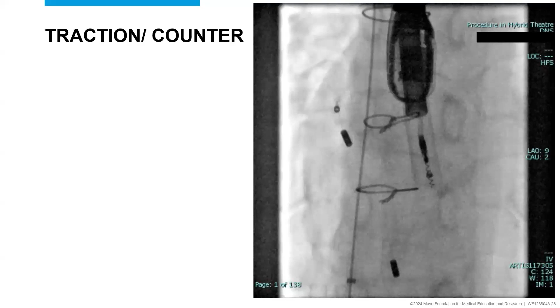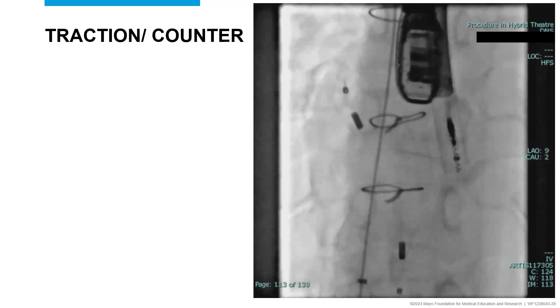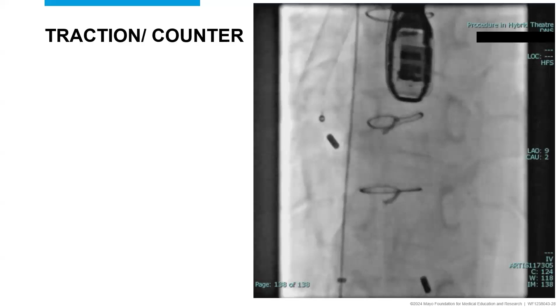And then now we've got the outer sheath on. You can see the TightRail is again there, and now we've got the outer sheath to the tip. We're putting pressure back on both of these. Another point that I think is important in my practice when we're talking about traction and counter traction in these circumstances: you're not talking about something going forward and something going backwards. You're talking about both of these going backwards, but you're just pulling more on the lead than you are on the sheath. So it's a relative counter traction as opposed to an absolute counter traction. Because when the tip is stretched out and it gives way, you want everything to come backwards. You don't want pressure on your outer sheath that suddenly jumps forward and potentially goes through the myocardium. So although it still makes you jump a bit when this jumps, or it makes me jump anyway, that's the direction you want things going when this lead comes out.